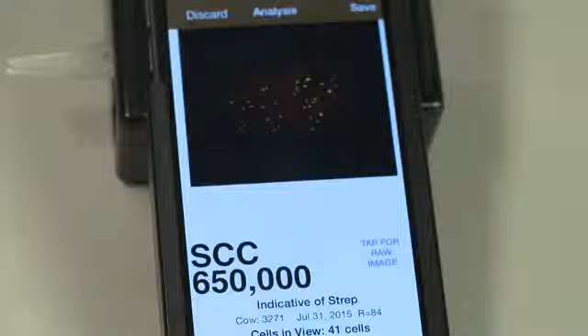On your first few tests, please make note of the Our Process screen. You will find useful information that will help you better understand your test results. You now have your test result. Cells in view refers to the cells counted, including clusters. R value refers to the relative brightness. A number below 100 hints at a degrading battery. Indication of pathogen refers to the potential bacteria causing the elevated somatic cell count. This will appear in counts above 300,000. Hit Save to keep the test stored in the memory of the iPod or iPhone.